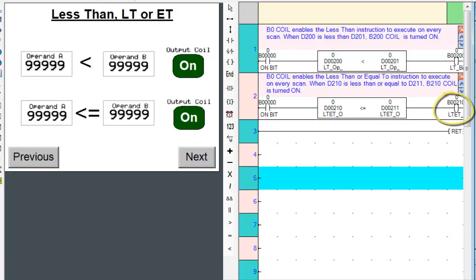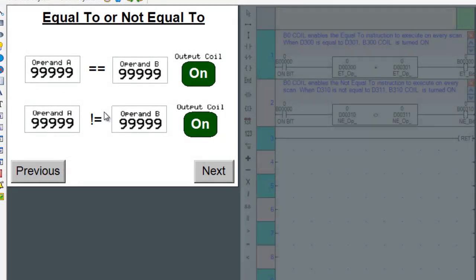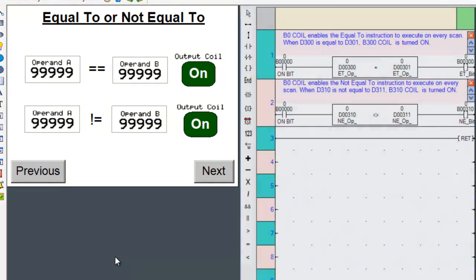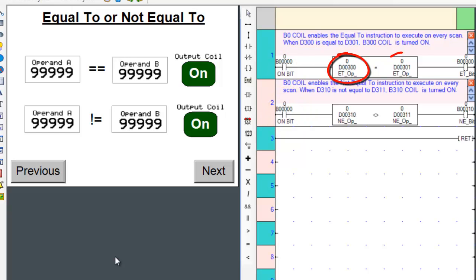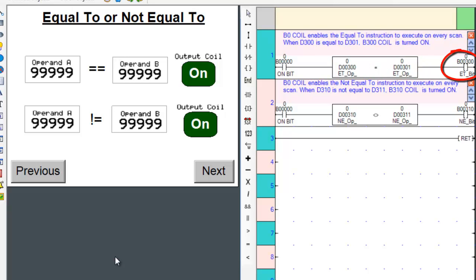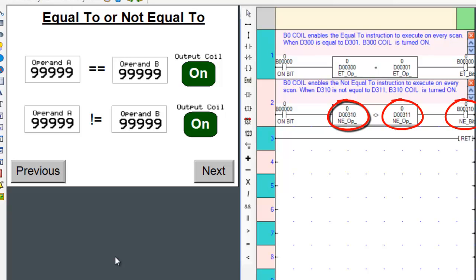Let's go to screen three and examine the equality operators. Let's also place the appropriate ladder logic subroutine on the right of the screen. The always-on coil enables the instruction to execute on every scan. So as soon as operand A is equal to operand B, it will turn on the output coil. The same is true for the not equal to operator — as soon as both operands do not equal each other, the output coil is turned on.